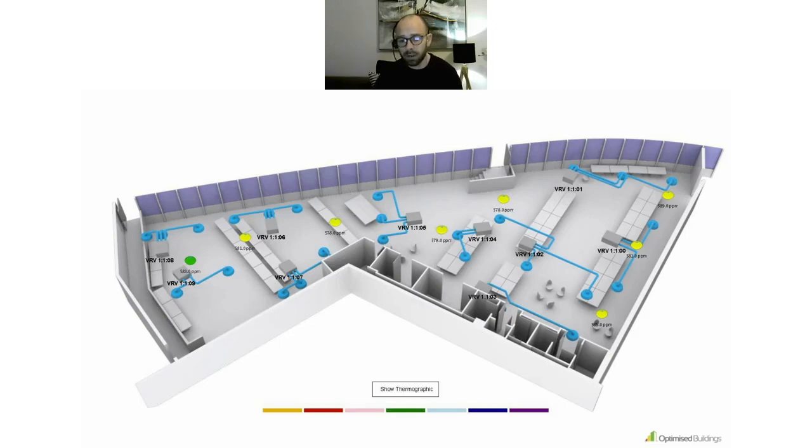So this is a view that the end customer facilities team have on the ground. You can see here the Airthings sensors, most of them are colored yellow at the moment, and there's one that's green. This is a snapshot that was taken a few days ago. And just to mention that this installation only went live about a week ago, so we're still understanding how it's performing at this point. The green would represent CO2 performing well, and the yellow would be okay, but could be better.